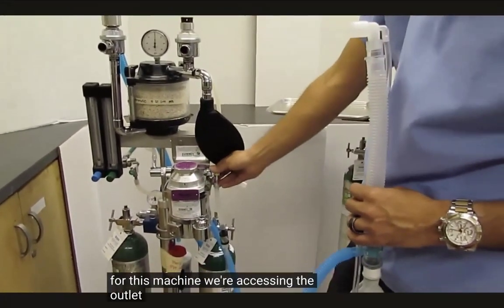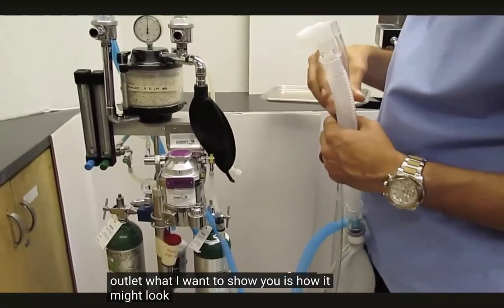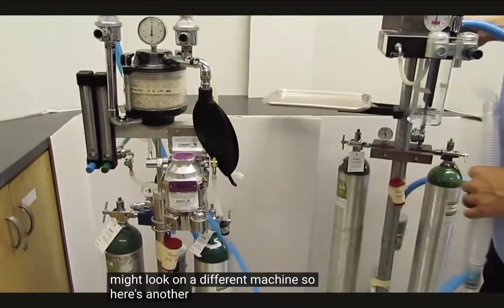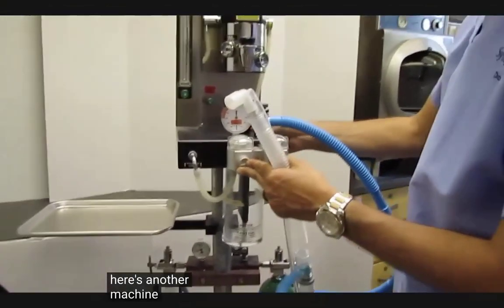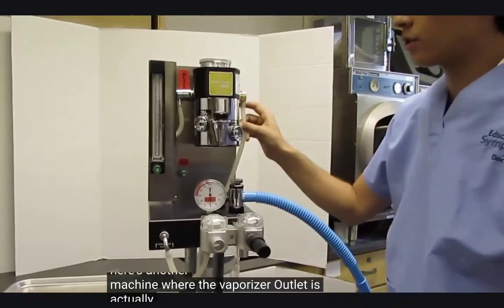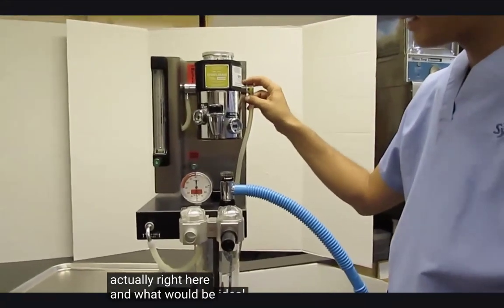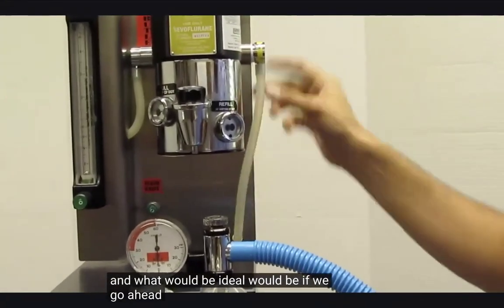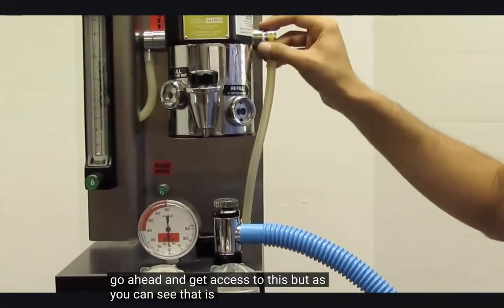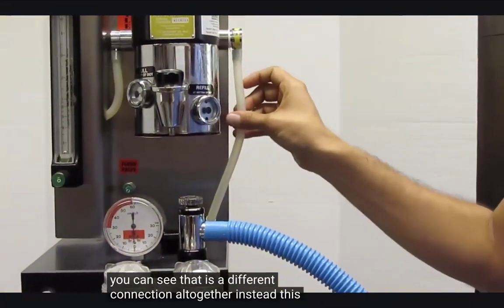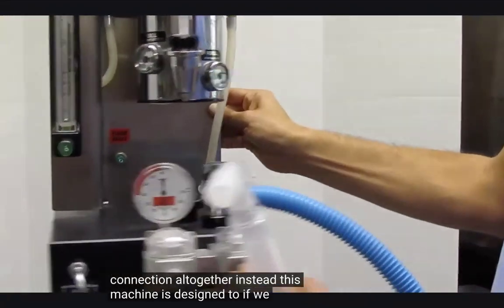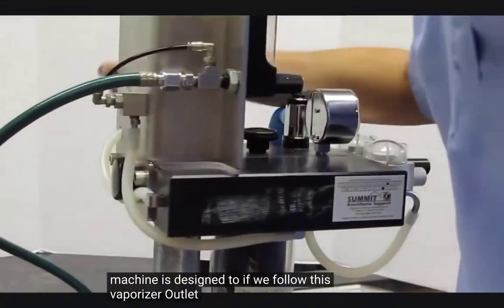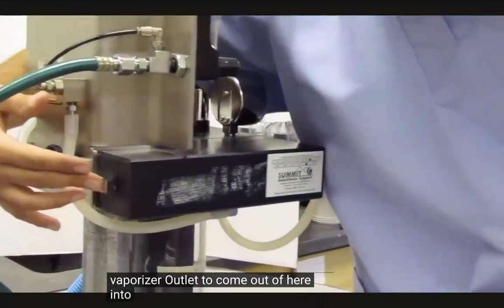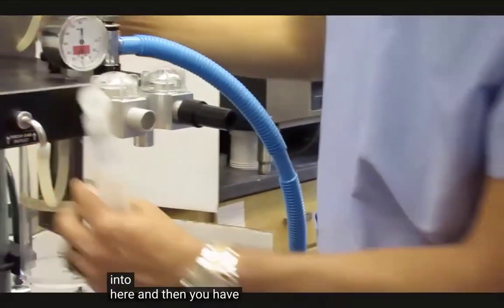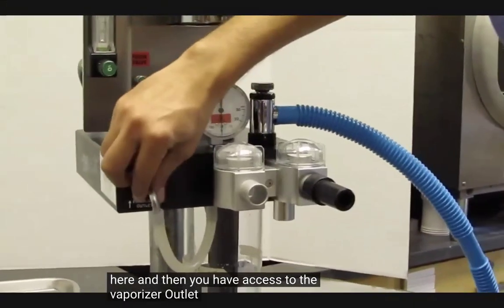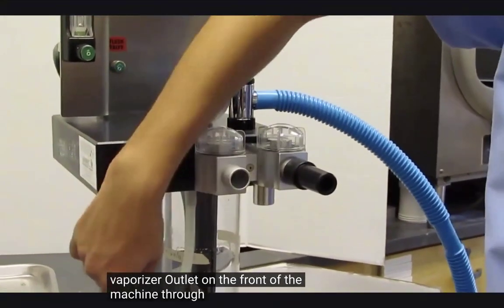We're accessing the outlet. What I want to show you is how it might look on a different machine. So here's another machine where the vaporizer outlet is actually right here. What would be ideal would be if we go ahead and get access to this, but as you can see, that is a different connection altogether. Instead, this machine is designed so that if we follow this vaporizer outlet, it comes out of here into here, and then you have access to the vaporizer outlet on the front of the machine through here.